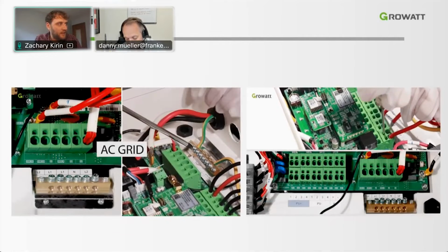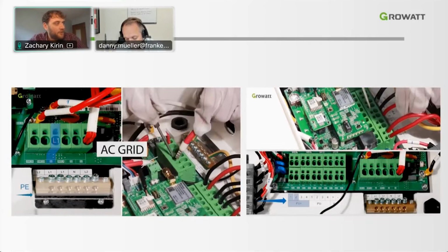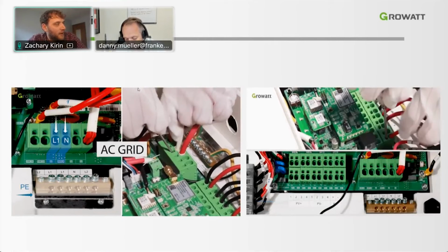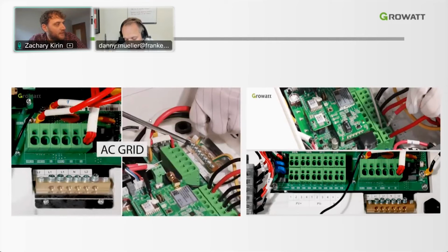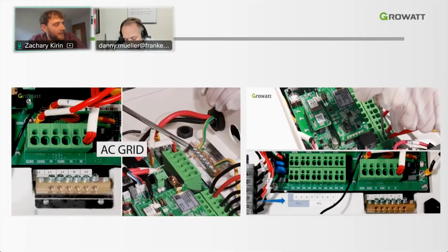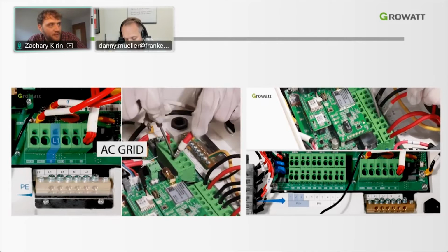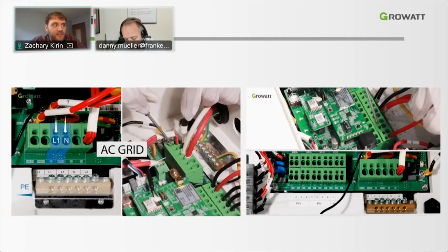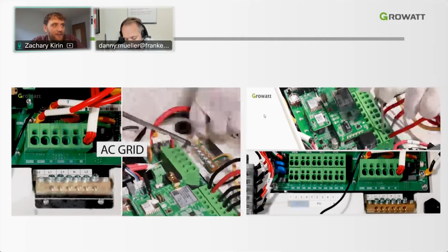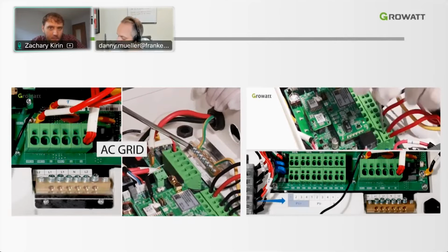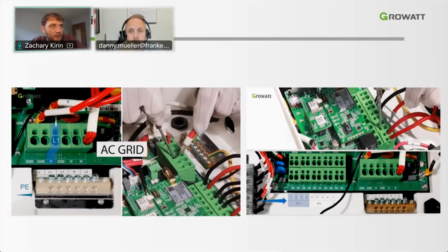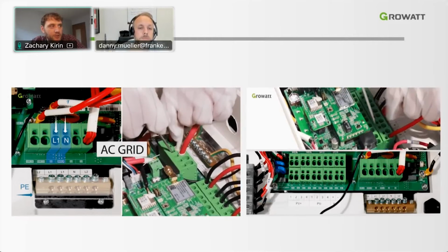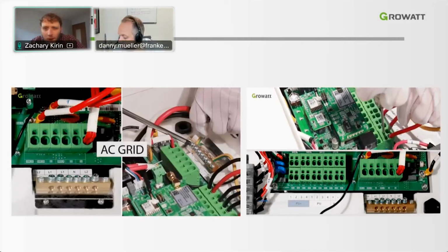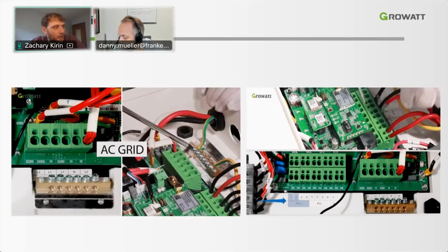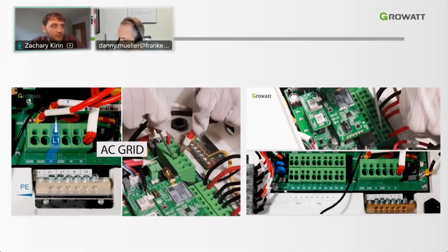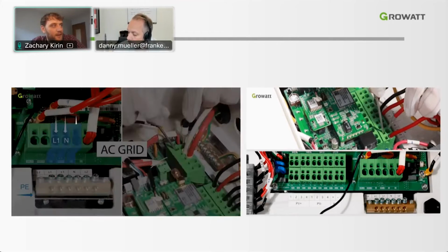The way to input the conductor to each of those terminals is utilizing your flathead screwdriver and then just releasing that clamp down and then plugging each conductor to the recommended terminal. And this is exceptional. This is extremely easy to install. It's no longer the case where we have to worry about those torque requirements, or about installing and making sure that everything is crimped in the proper manner and enough wire has been stripped off. Instead, we made it really easy for you. Just go ahead, insert a screwdriver, and then just input the conductor as such.